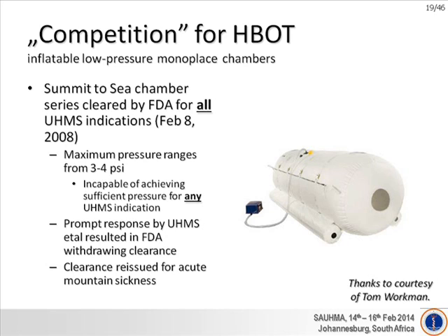temporarily they had been accepted by the FDA for all indications by the UHMS, enlisted by the UHMS, even if they were incapable of reaching any pressure which is necessary to do the hyperbaric treatment. Fortunately, following a prompt response by the UHMS, the FDA withdrew this clearance for those hyperbaric chambers, but still they are offered for private hands.